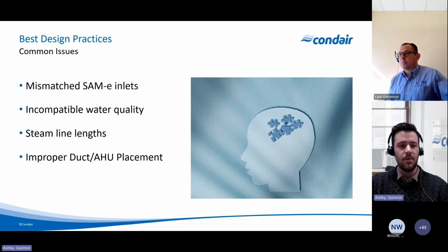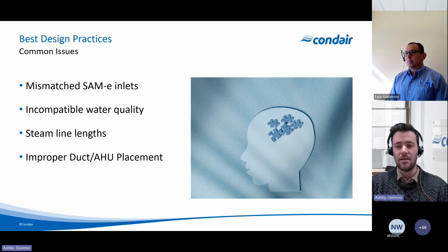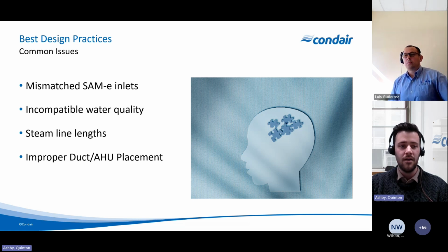I touched on this a little bit, but incompatible water quality: we want to make sure that we're looking at the water quality before we size and select the units, and then definitely before we install them. So very important. Same thing with steam line lengths. We want to make sure that we're looking at it. You may actually have to upsize the humidifier to get the steam line length that you want. You could talk to your Condair representatives about what that would mean and how it would affect performance, but typically there are ways to mitigate, though it's definitely something we want to look at. And then finally, improper duct and air handling unit placement. So the placement does matter. It will affect performance, and we want to make sure that we're doing it in the most optimal way possible.